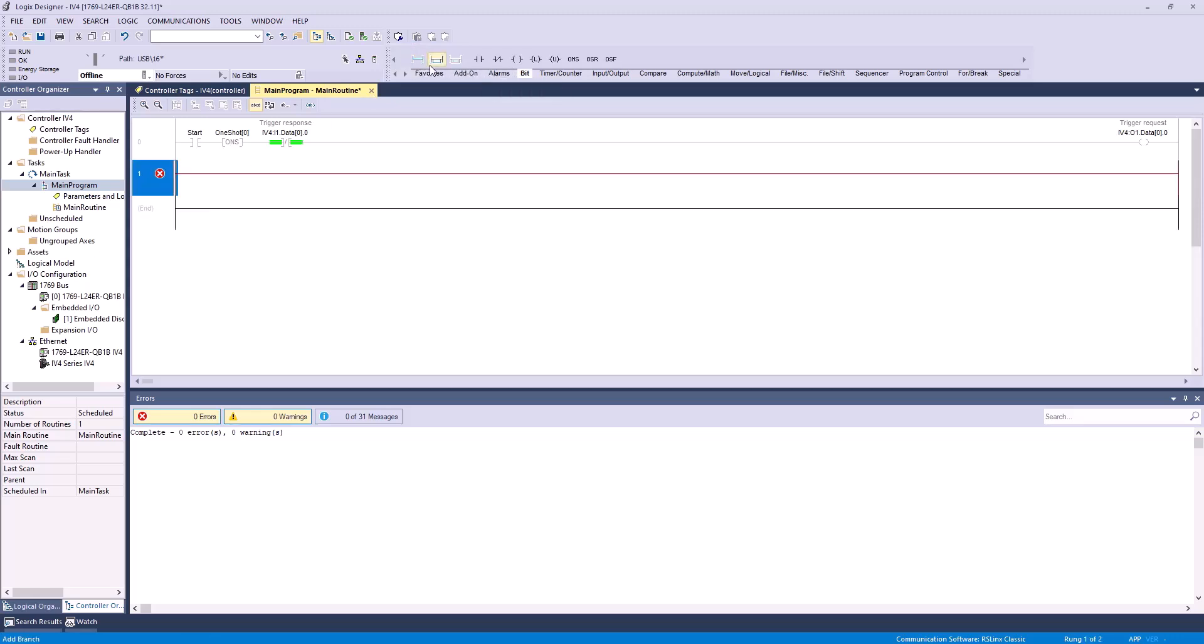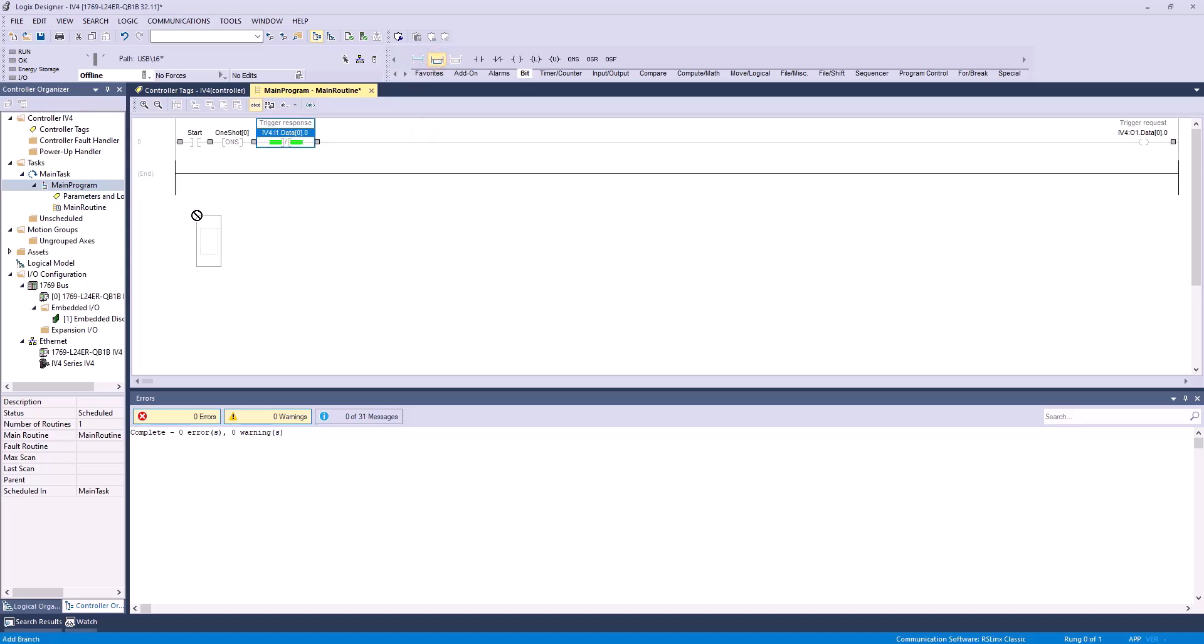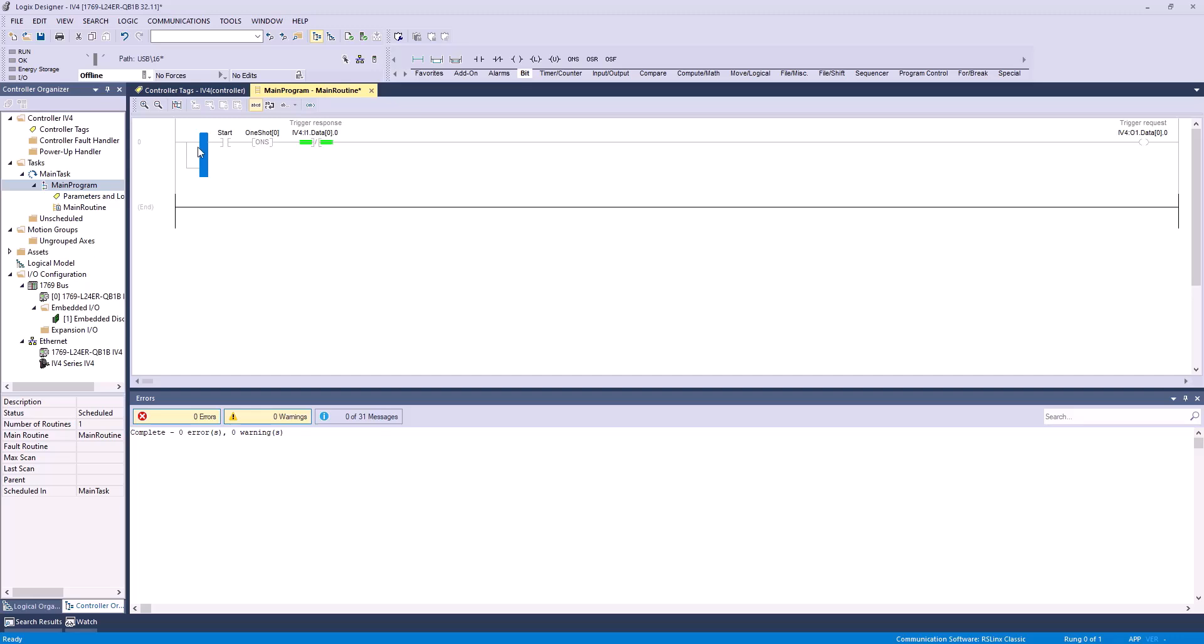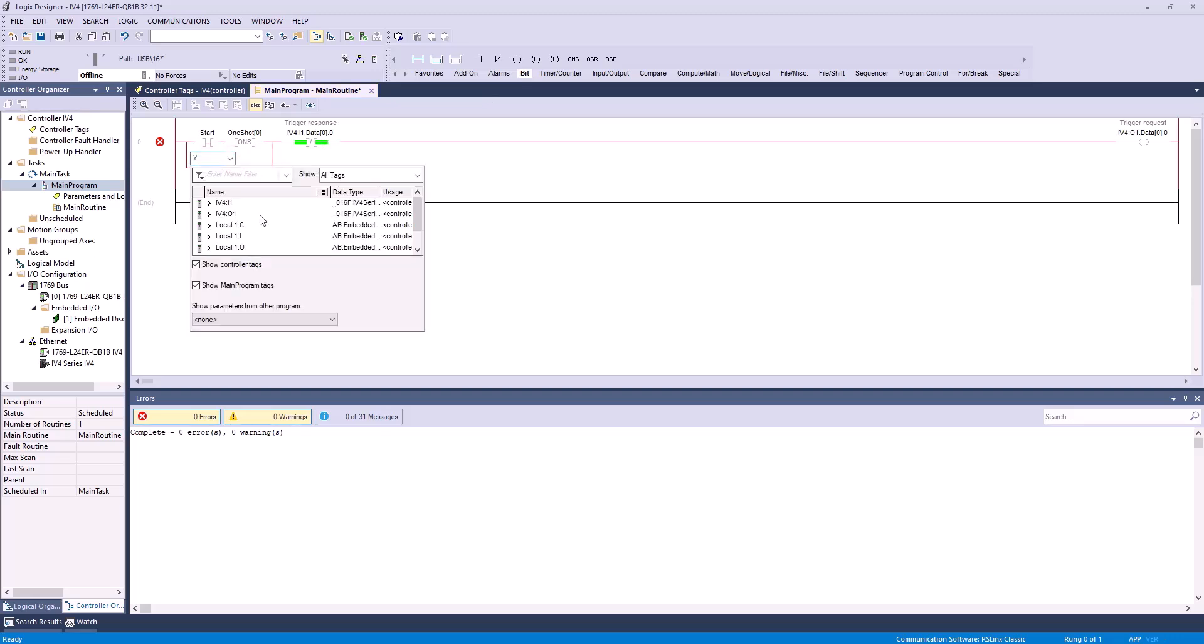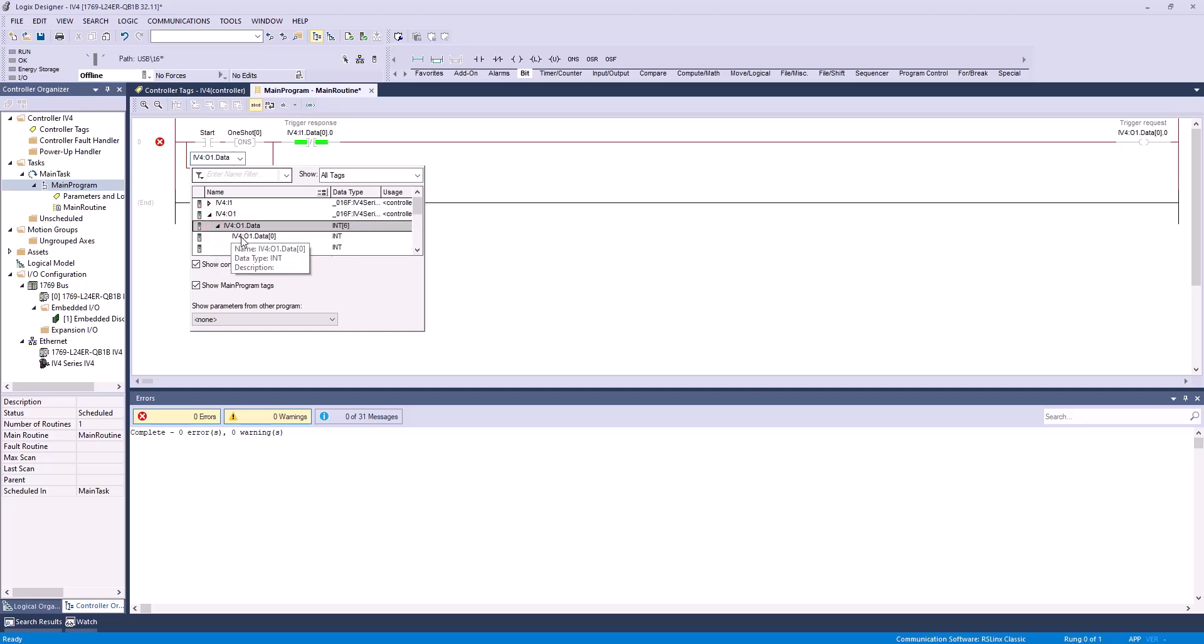Last thing we'll do is we need to add, not a rung, we need to add a branch. So, select this rung, and we're going to add a branch starting here, and we're going to pull it all the way past the one-shot. This gives an alternate path for this rung to become activated, and so we need another examine if closed bit. And this one we're actually going to also assign the same thing we assigned our coil to, output data 0.0 for our trigger request.